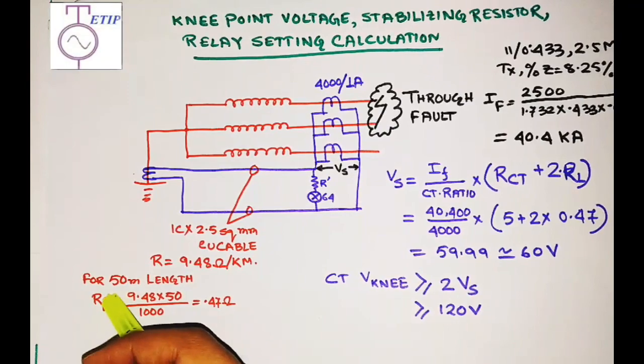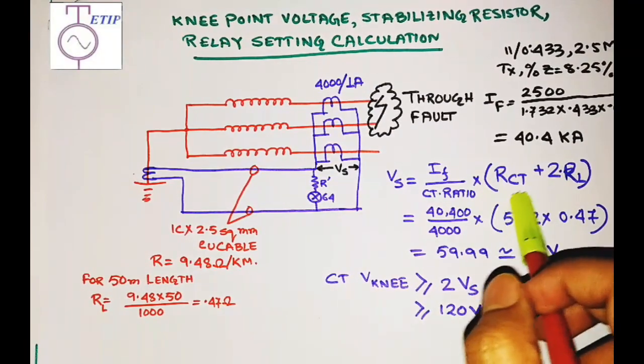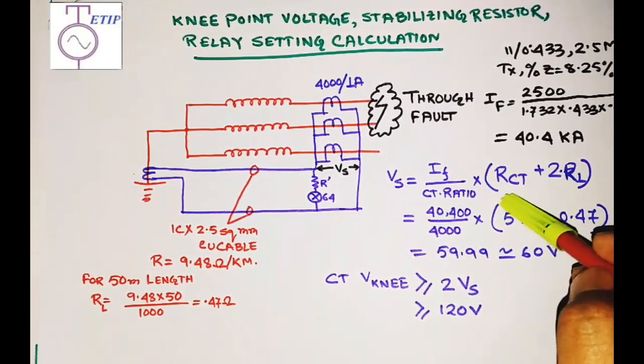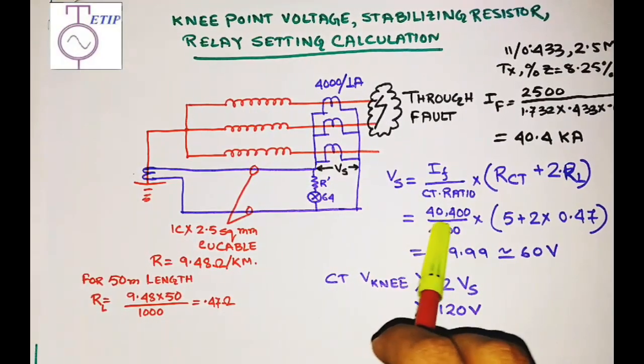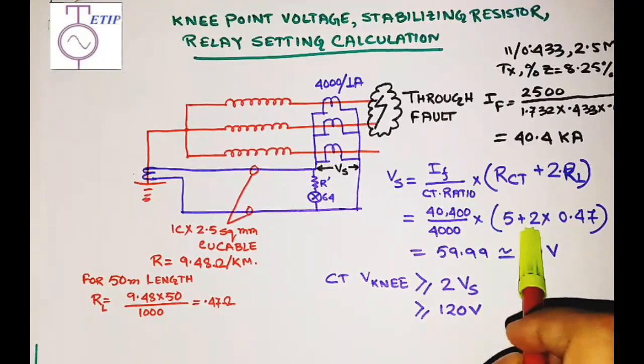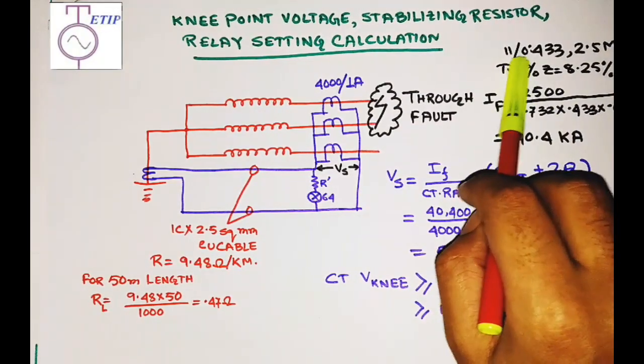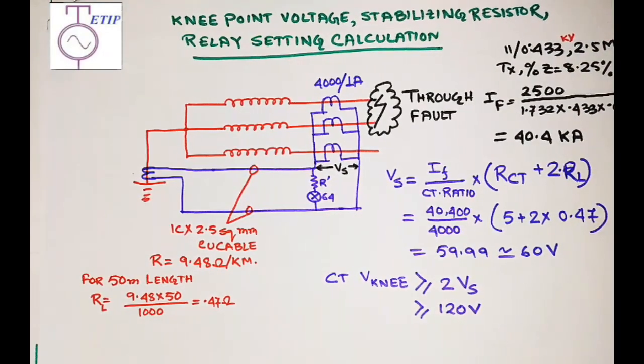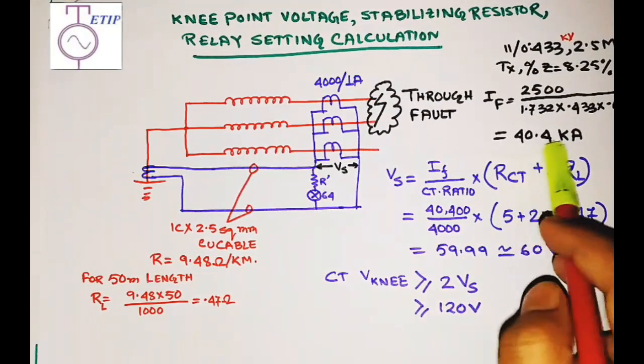You have to calculate Rl as per your project — whatever the cable length is applicable at site. You also specify Rct at the maximum value; in this example I have set it at 5 ohm, meaning I specify to the CT manufacturer that the CT resistance shall not exceed 5 ohm. For this example, using an 11 kV / 433 V, 2.5 MVA transformer with a percentage impedance of 8.25%, the calculated fault current is approximately 40 kA.